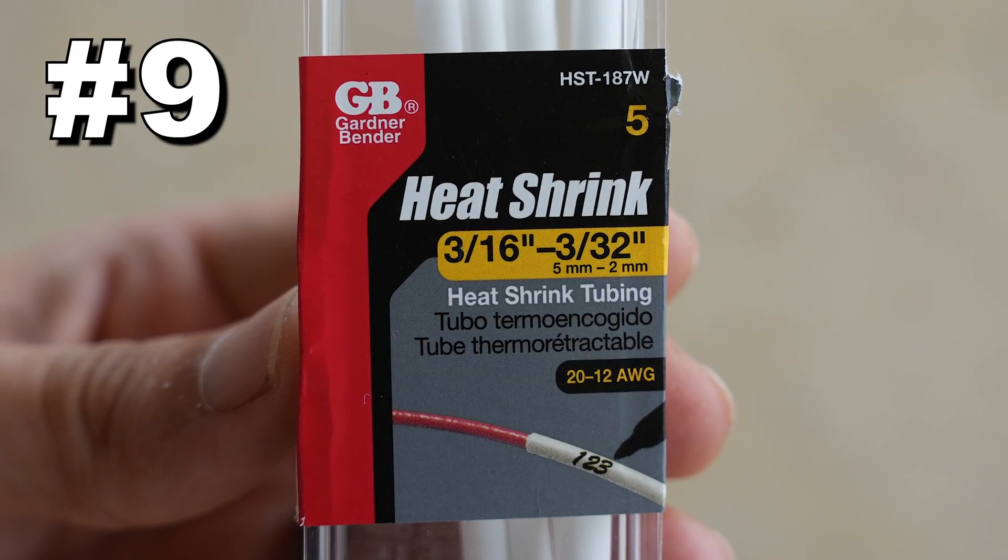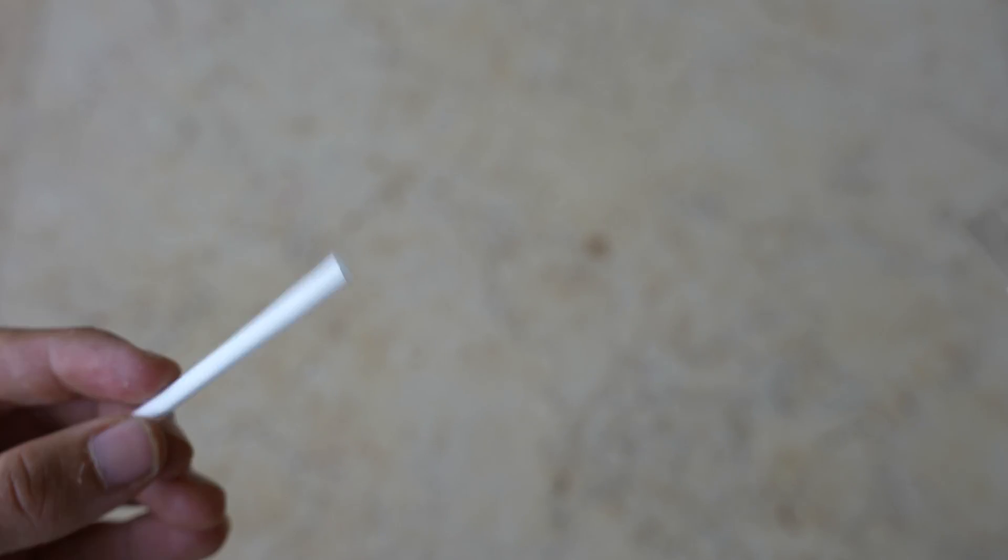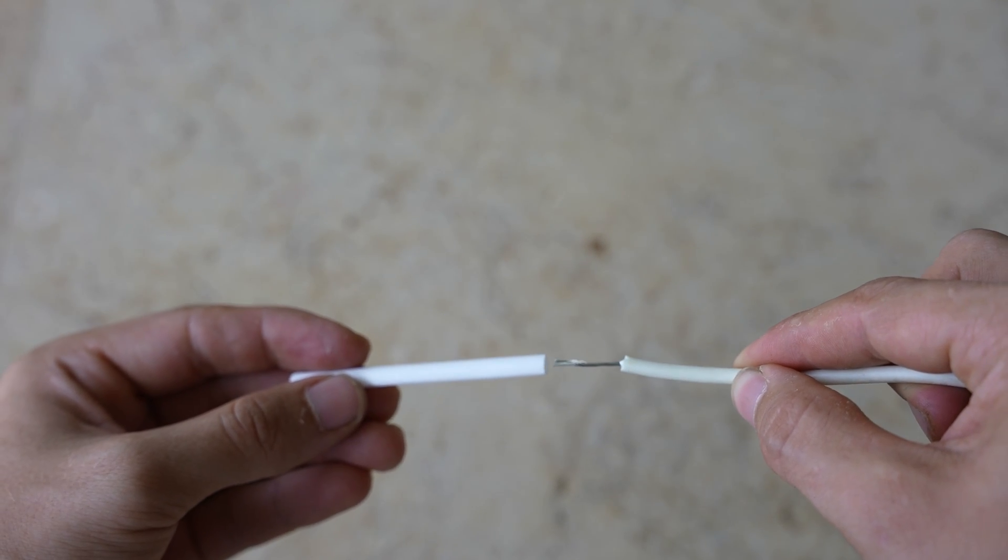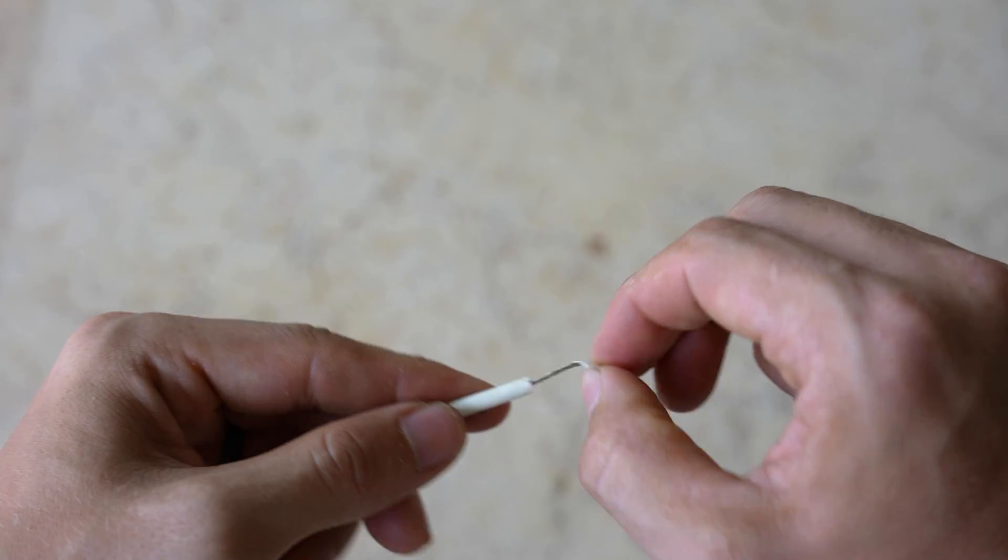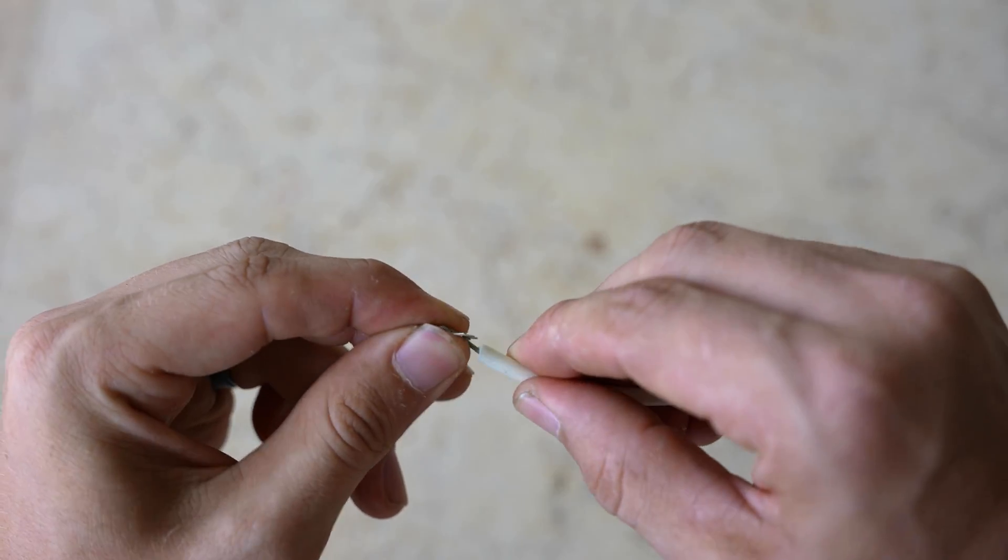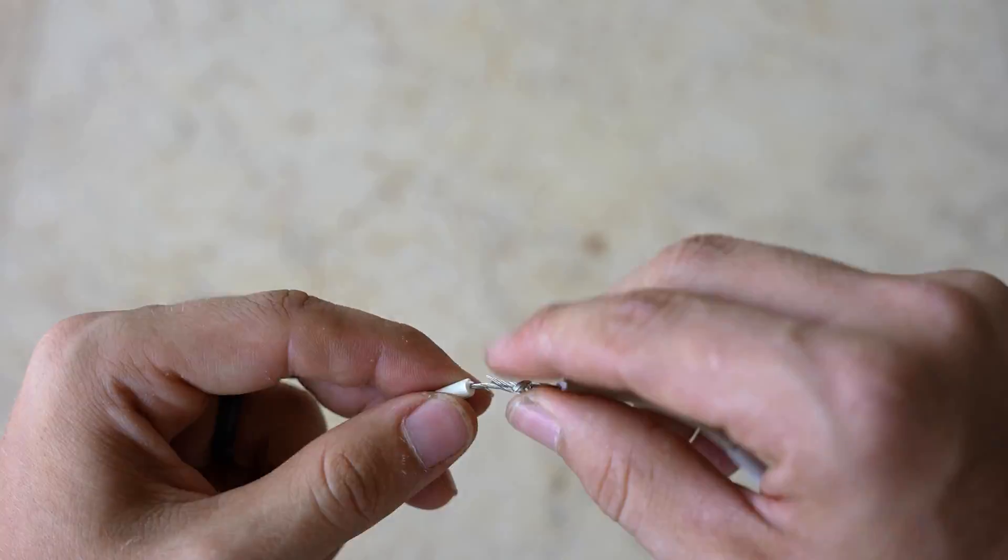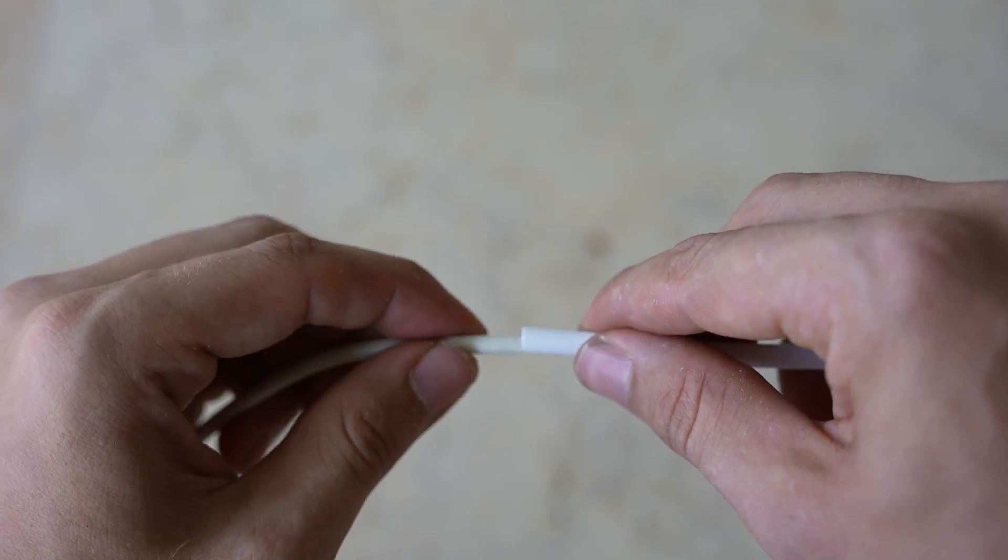Method nine is heat shrink tubing. I like this one the most because it's the cleanest looking repair out of all of them. To begin with, slide the tube, or two of them, onto the wire. Then, bend both bare wires into hooks and hook them onto each other. Next, take the ends of the wires and wrap them around themselves. Now, we are ready to slide on the heat shrink tube and apply the heat.